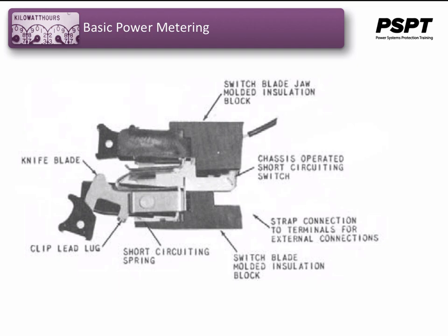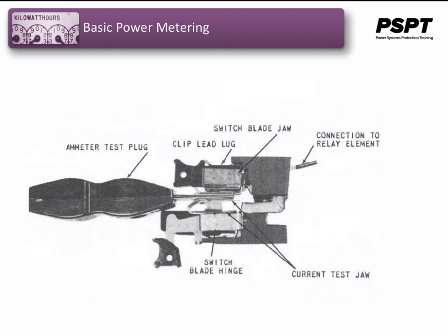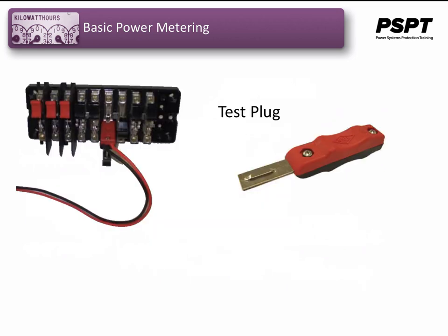And you can see here a side view of the test block where the switch is open, but the connection to the meter is still maintained through spring-loaded connections. And as the test plug is inserted, it makes connection with the bottom and the top of the switch, and the current will then flow through our test plug connection.